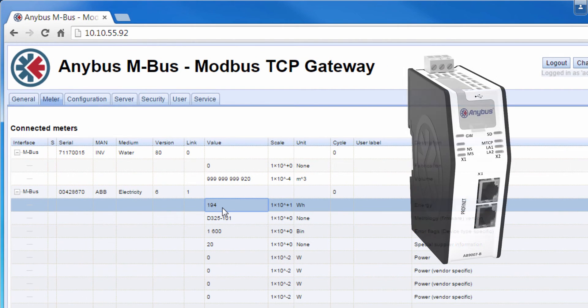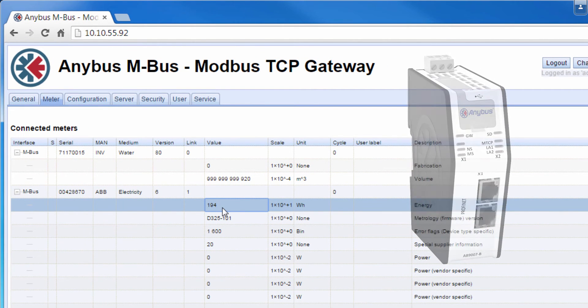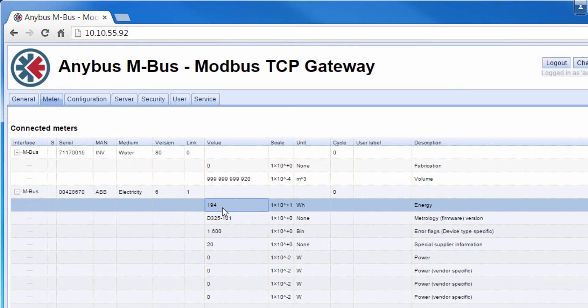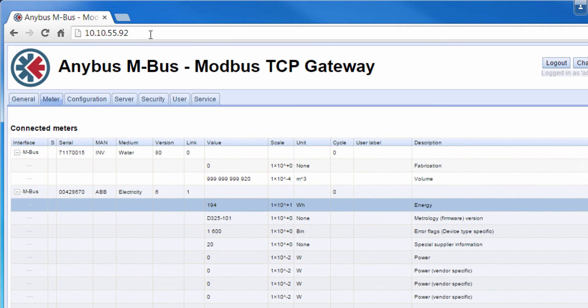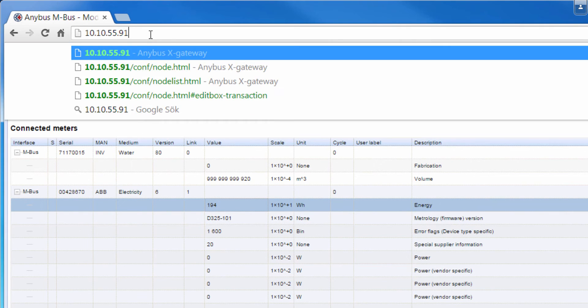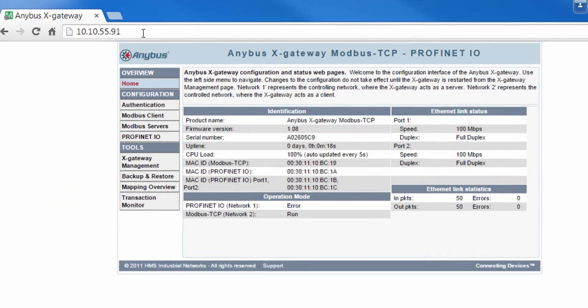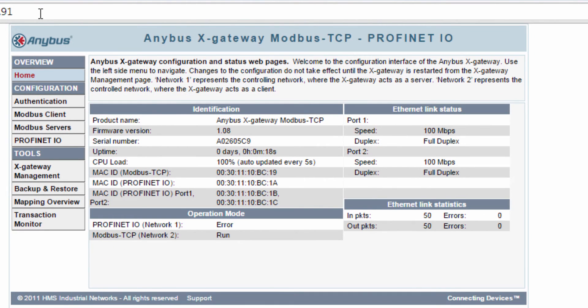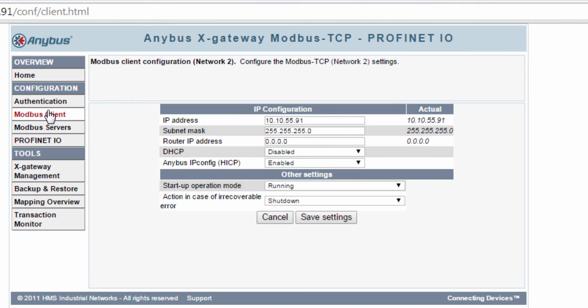To receive these values, I will use the Anybus X-Gateway Modbus TCP. The configuration for this gateway is also web-based, so I can simply type in the IP address of the gateway, which in this case is 10.10.55.91. Now I have landed in the Anybus X-Gateway Modbus TCP to Profinet.io. By clicking on Modbus Client in the navigation to the left, I can change IP addresses and other general settings for the Modbus client. Client means master in Modbus terms.